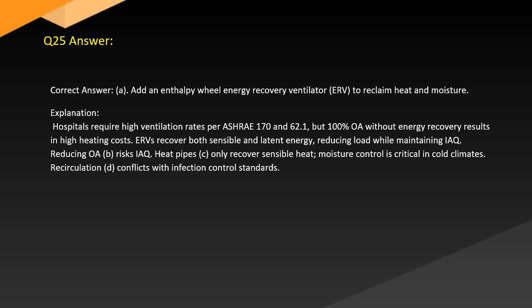Explanation. Hospitals require high ventilation rates per ASHRAE 170 and 62.1, but 100% OA without energy recovery results in high heating costs. ERVs recover both sensible and latent energy, reducing load while maintaining IAQ. B. Reducing OA risks IAQ. Heat pipes, C, only recover sensible heat. Moisture control is critical in cold climates. D. Recirculation conflicts with infection control standards.